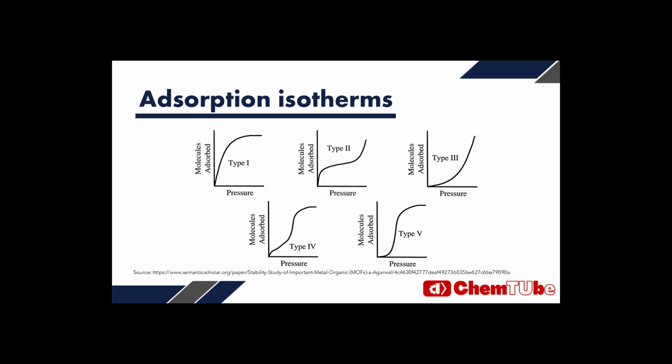The output of the analysis are adsorption isotherms. They show the amount of molecules adsorbed by a pretreated, so initially clean, solid surface at constant temperature and equilibrium pressure. For every pore size, different isotherm behavior will be observed. On the y-axis, the mass or volume of adsorbate normalized to standard temperature and pressure, STP, is expressed. On the x-axis, the dimensionless relative pressure, the ratio of the pressure at which the measurements were made to the saturation pressure at the temperature of analysis, is expressed.